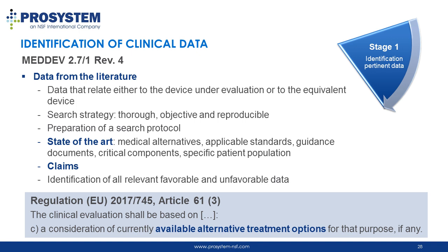Sources of pertinent data also include data from the literature. This data can be related to either the device under evaluation or to the equivalent device. To obtain this data, a thorough, objective, and reproducible search strategy needs to be developed. Following this strategy, a search protocol should be prepared.